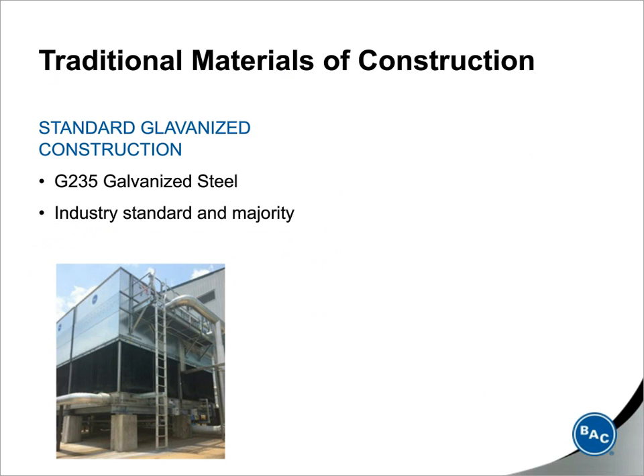Traditionally, factory-assembled cooling towers have been constructed from either galvanized steel with a thermosetting hybrid polymer coating, that's a powder coating, or stainless steel. Now, galvanized steel offers the most basic level of corrosion protection. Then, by adding a thermosetting hybrid polymer, again, it's a powder coating, you're adding another layer of protection, and also you don't need to passivate a tower that's coated with a protective coating.